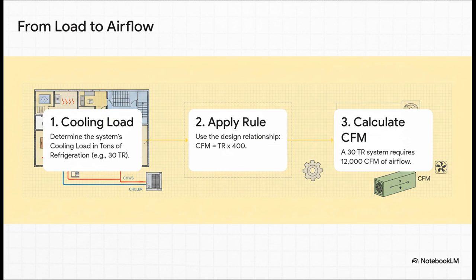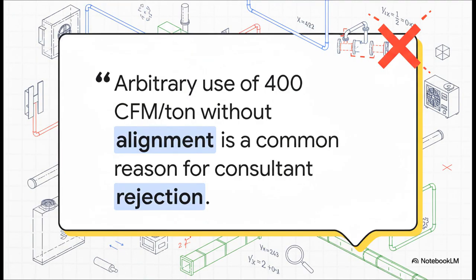That's our target. But, and this is a huge but, you've got to be careful here. This is a classic rookie mistake and a massive red flag for any consultant reviewing your work. You can't just blindly throw that times-400 rule at every project. You have to be able to justify it. Does it align with the energy goals? What about fresh air requirements? Without that solid reasoning, your design is going to get stamped, rejected, faster than you can say CFM.